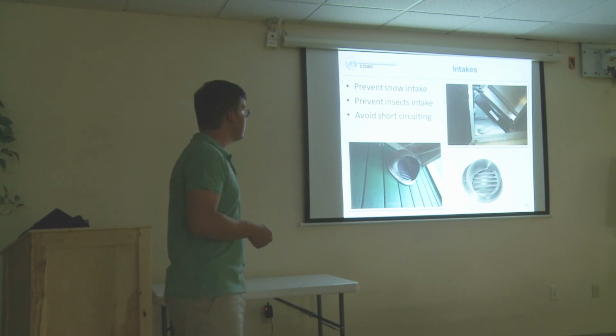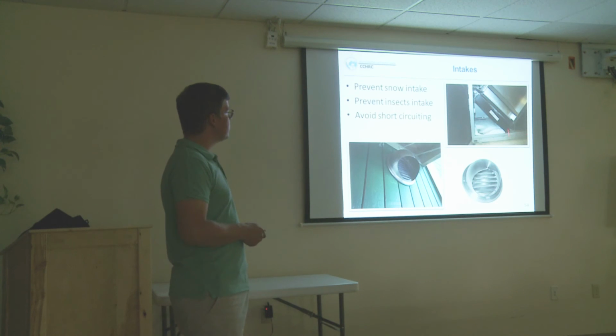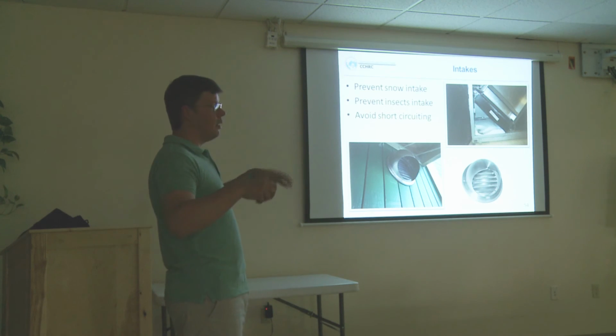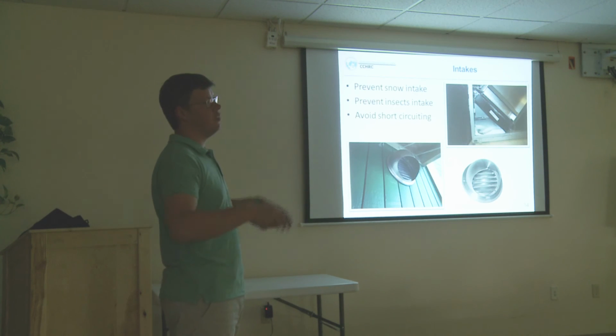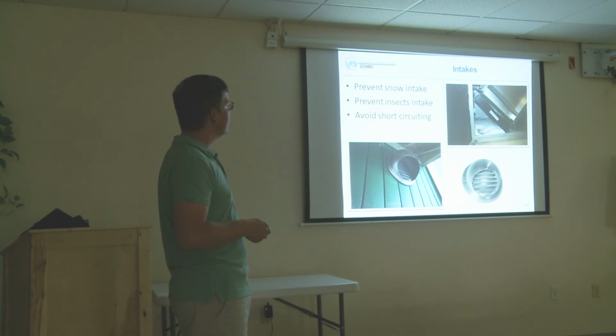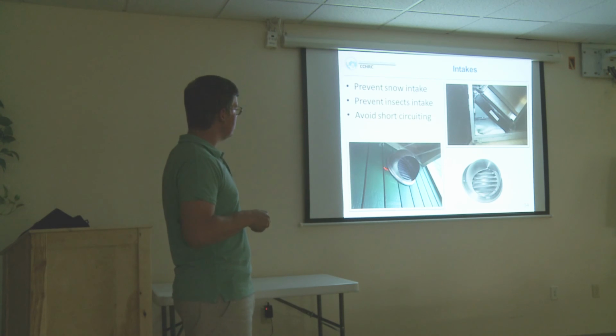Very important are the intakes on the facade. We have seen lots of pictures where, especially when it's so cold and the snow is so light, an improper intake lets lots of snow get transported to the ventilation unit, and eventually it can block the whole unit. So intakes have to be protected, and can also have nets to avoid insects entering. It's important to put them as far apart as possible, because otherwise there is a risk of short circuiting, where the exhaust air would be taken in again.